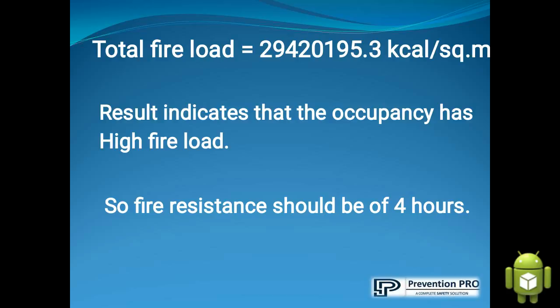So, the total fire load value that we have got was 2,94,20,195.3 kilocalories per square meter. This result indicates that the occupancy has high fire load, so fire resistance should be four hours.